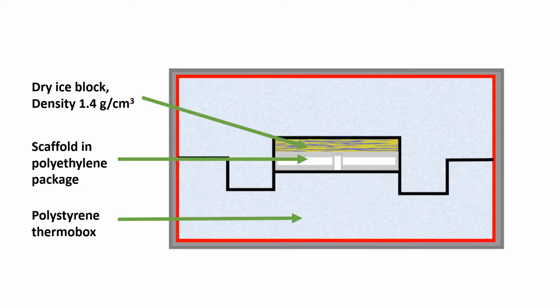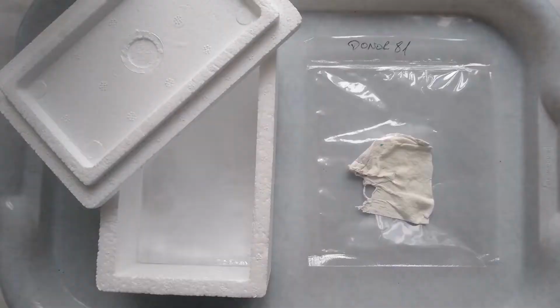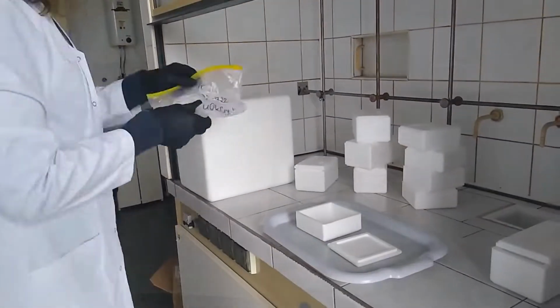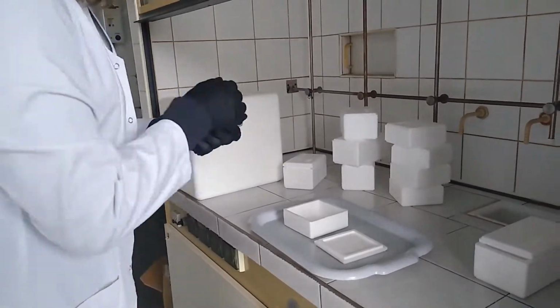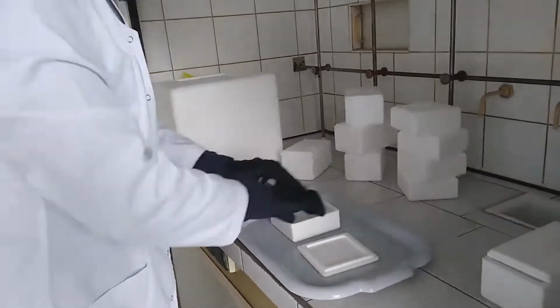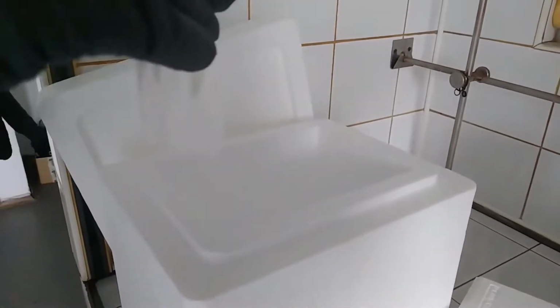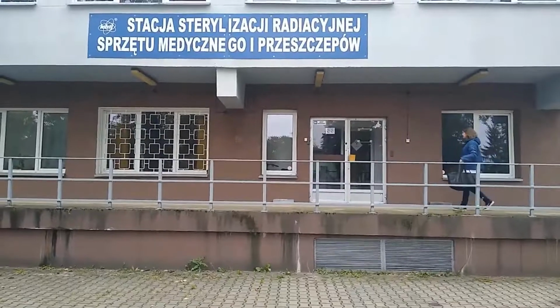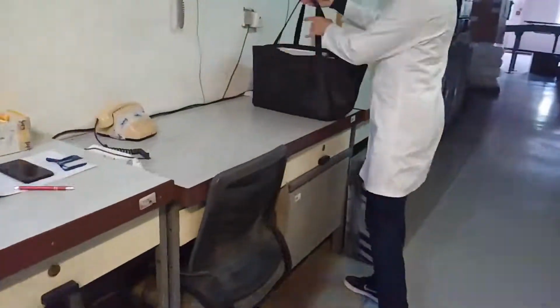The dressing placed in such a tight package is sterilized using an electron beam of the energy of 9.5 megaelectronvolts, with the dry ice layer faced towards the electron beam. The dimension and design of the package enhance the electron beam dose deposition. The parameters of the packaging were optimized and the dose distribution in the sterilization device was calculated and experimentally validated. The maximum number of allografts that can be placed in the sterilization device was determined.